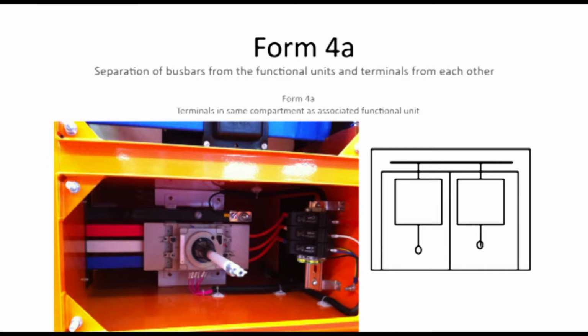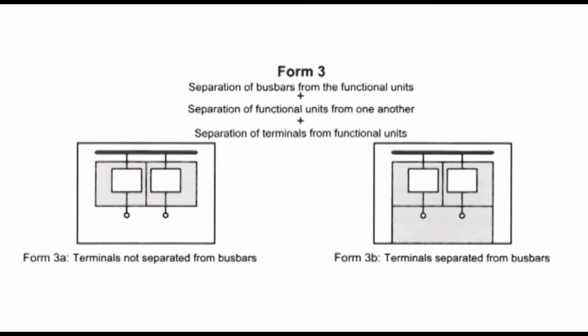It is perfectly acceptable to specify a Form 3B switchboard, but that is when the ability to turn the entire switchboard off is available before any electrical work is conducted. Unless the switchboard can be fully isolated, it places an electrician in a dangerous workplace. It means an electrical worker opening a cable chamber will be faced with live, unprotected outgoing terminations. I ask, what are our obligations to OHS and a safe work environment that are required today? Is a Form 3B switchboard acceptable?